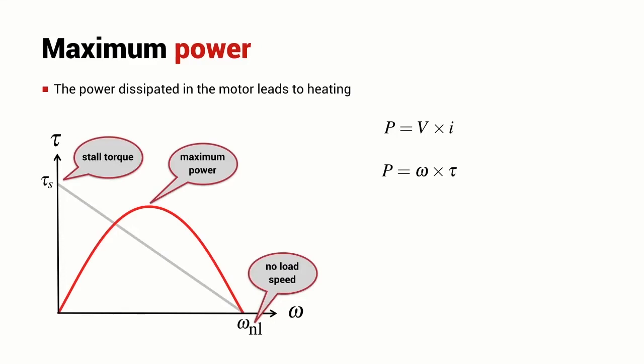Power is a quadratic function of speed. It has a maximum somewhere in the middle of the operating speed range of the motor and the motor cannot be operated for a sustained period of time above its maximum power rating else it will be damaged through overheating.